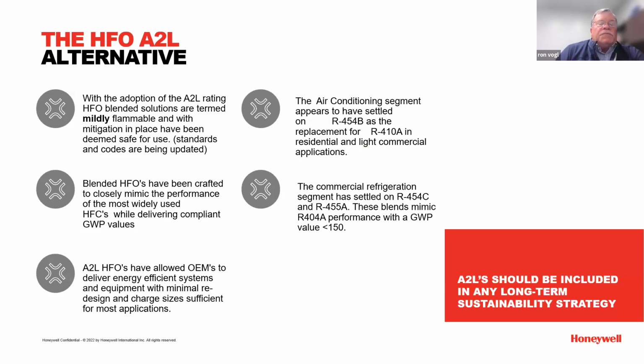So why A2Ls? I'm not going to read all these things on the slide, but I'd already mentioned that there's a lot of replacements. And the replacements that the industry, Honeywell and others, is able to come up with really mimic the A1 refrigerants. 454B and 32 mimic the performance of 410A in equipment. What that means to an OEM building equipment is they don't have to do much in the way of re-engineering. So in other words, someone's building a 410A unit and they're going to go to 454B. Most likely they don't need a different compressor. They don't need a different evaporator, condenser, line sizing, anything like that.